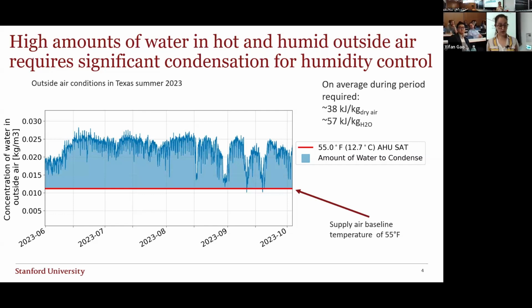But we needed about 57 kilojoules per kilogram of water to cool down the water and condense the excess humidity. So the energy needed for the humidity part is actually much larger than for the dry air part. The amount of water in your air, mostly outside but also indoors, can be a big driver of how much energy you consume running your HVAC system. At this location during this time period, the blue line never really crosses the red line, so it doesn't actually matter that the red line is constant.